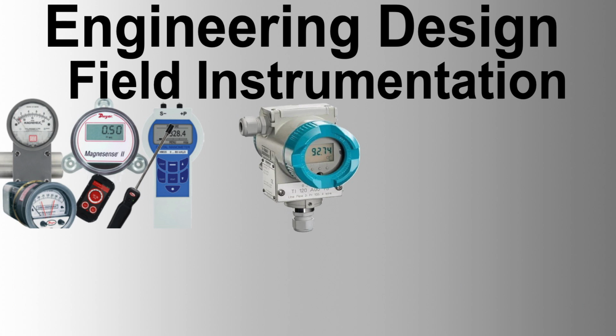Instrument transmission signals. Signal transmission between field instruments and remote control systems equipment, e.g. ESD and RTU, must generally be electric as follows. Analog transmitters, 4 to 20 milliamps, 2-wire, 24-volt DC, smart HART digital communication preferred. Control elements, 4 to 20 milliamps, 2-wire, 24-volt DC, smart digital communication preferred, power sourced from ESD RTU. Temperature element, other than temp transmitters, 3-wire PT100 RTD.